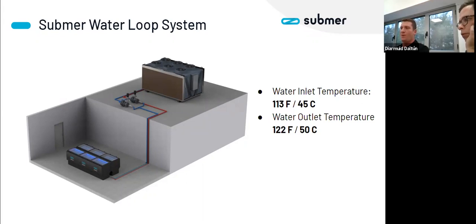But the water temperatures that we would typically operate our systems at range between 113 Fahrenheit and 122 Fahrenheit, which we can also raise, and this really depends on the type of hardware being deployed as well, and on the region. But it really does mean that we can use dry coolers practically anywhere on the globe, and there's a substantial saving in that part of the infrastructure and the maintenance of that infrastructure, because it's just much simpler to deploy and maintain.